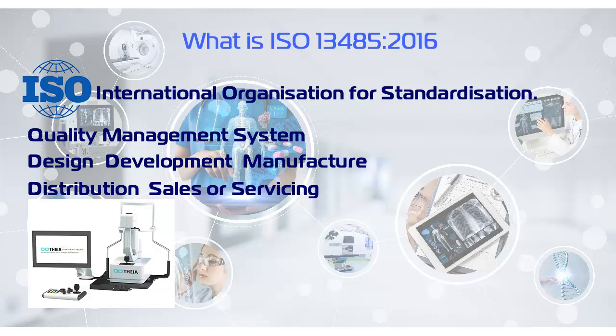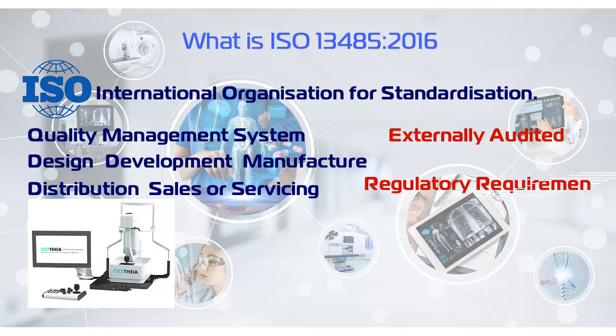By certifying an organization as conforming to the ISO 13485 standard, an accredited third-party body of auditors attests to the organization's conformance to the quality management requirements of the standard, including being compliant with applicable regulatory requirements which must be identified within the Quality Management System, or QMS. If you are in any way familiar with ISO 9001, you will see that there is a lot of overlap across these two standards. The colon 2016 refers to the year that the revised standard is published.